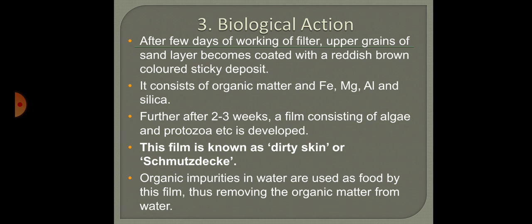Like I told you, after a few days of working, the sand layer at the top will become coated with a reddish brown colored sticky deposit. As the water keeps passing through the filter medium, a sticky deposit will be formed at the top. This deposit consists mainly of organic matter and also iron, magnesium, aluminum, silica, etc. All this that is present in the water will be deposited at the top layer.